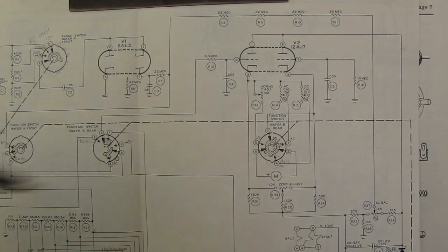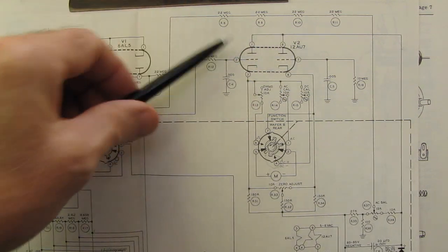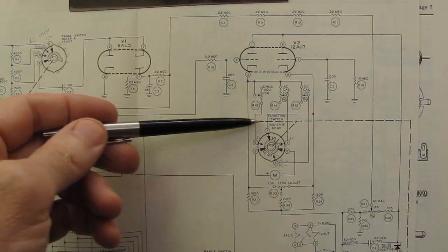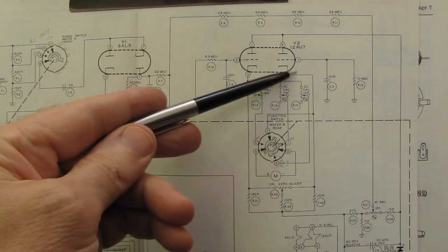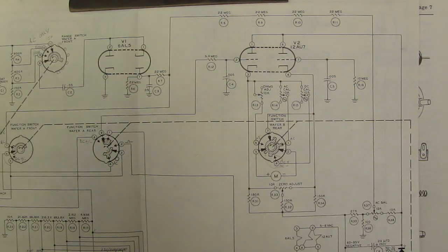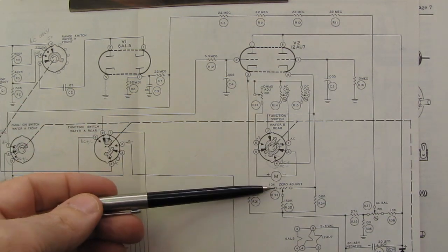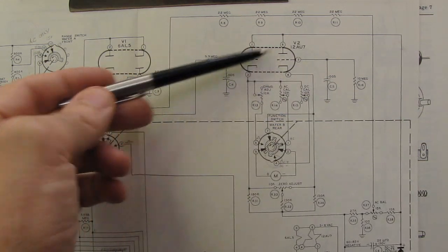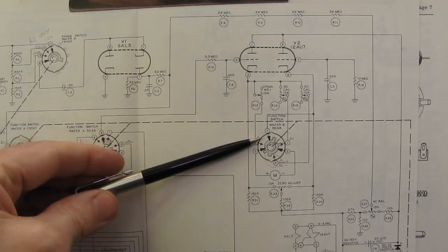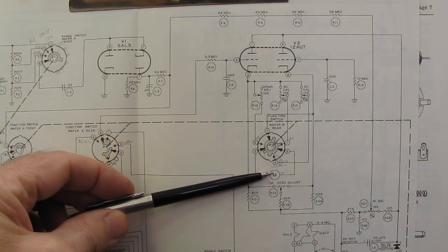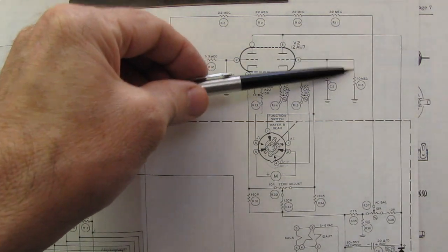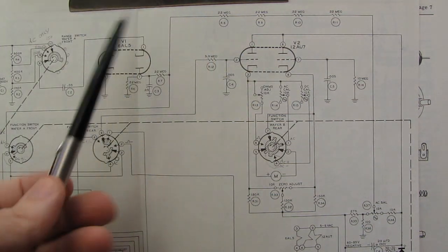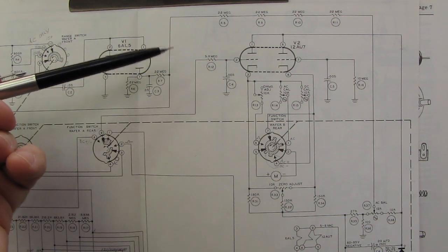So here we are, this is the bridge circuit that controls the meter, the meter's right here. And the meter is connected through this switch and through some resistors to the two cathodes here. And the way it works is the bridge zero balances here, it balances the current on these two cathodes.